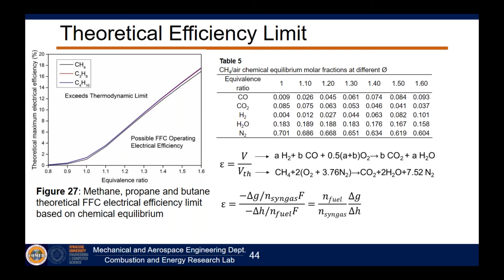Conventional burners, the kind used in your furnace or boiler, have what's called a rich limit. I've already talked a bit about that, it was 1.4 in our particular setup. They also have a lean limit. You can't get too lean either, otherwise the flame will extinguish.